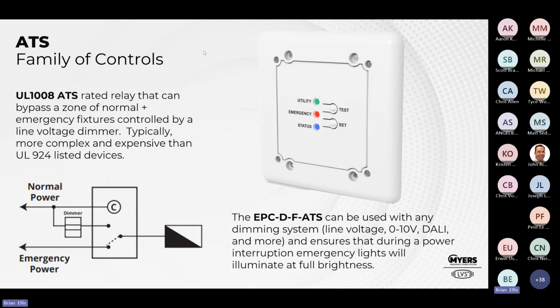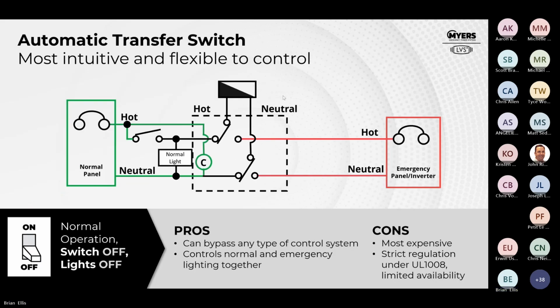Moving on to the automatic transfer switch. This device is very different because if you look at the wiring of it, this emergency light or zone is not on the emergency switch leg side. It's actually off of the device itself. Whenever you're looking at a wiring diagram, if you want to understand if it's an ALCR or an ATS, it's very simple. If the light fixture is fed from the device itself and it's being fed from two sources of power, it's very much a UL1008 transfer switch. It is not a bypass relay.